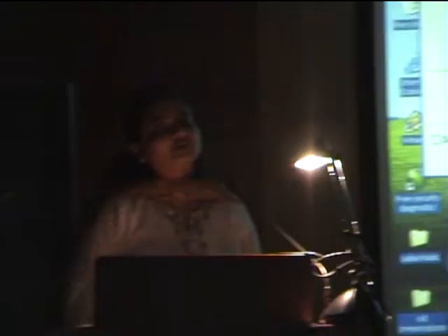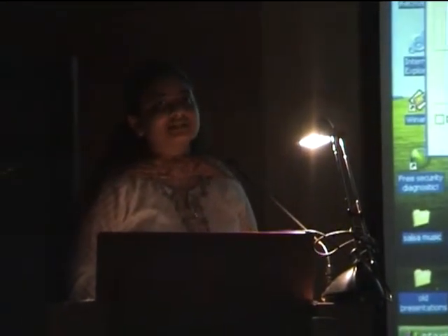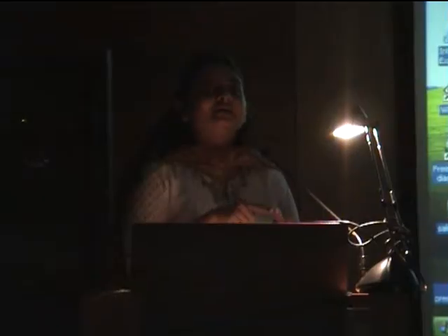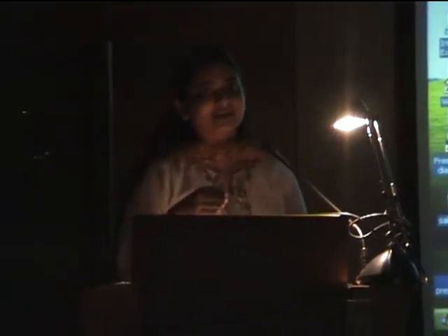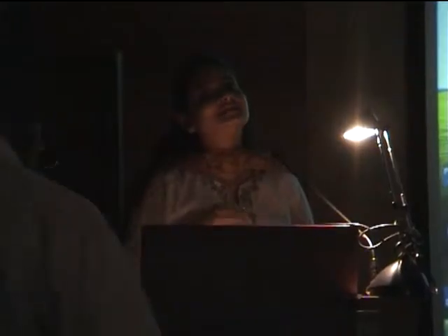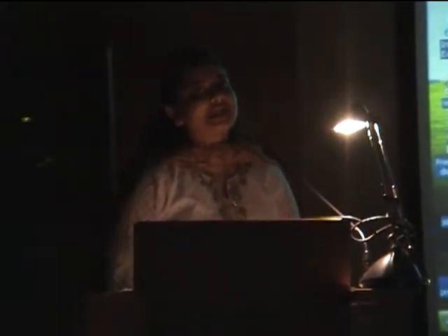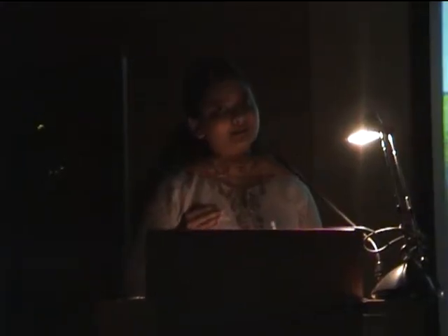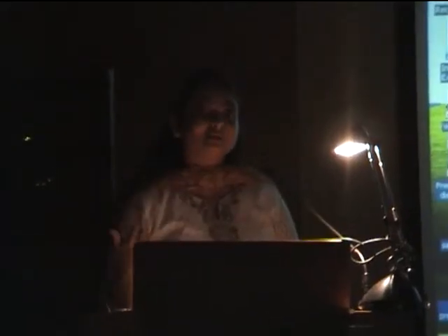Plus, if you are giving too much electrical current, there are chances that the current will be splashing around to the other electrodes and then the signal clarity is not going to be there. So we try not to give too much amplification, and keep it at a level where the person is comfortable. If we go on stimulating, since the other nerves are also nearby, there are chances of stimulating those nerves, and you can stimulate the facial nerve, you can get some facial twitching, etc., which you don't require. That is why we need to keep it within the comfort level and not go beyond.